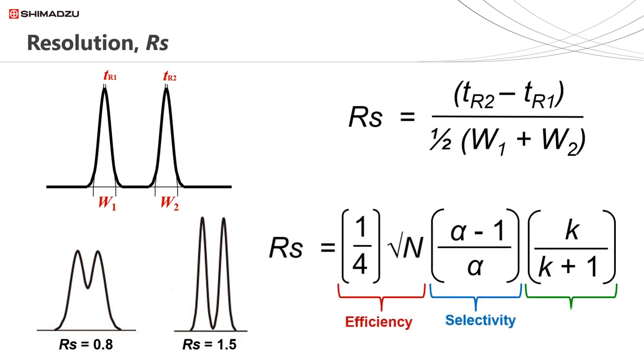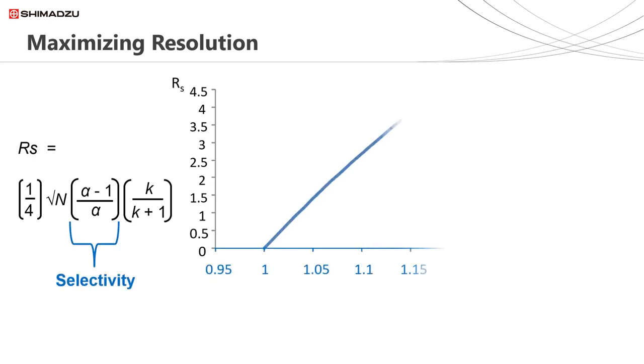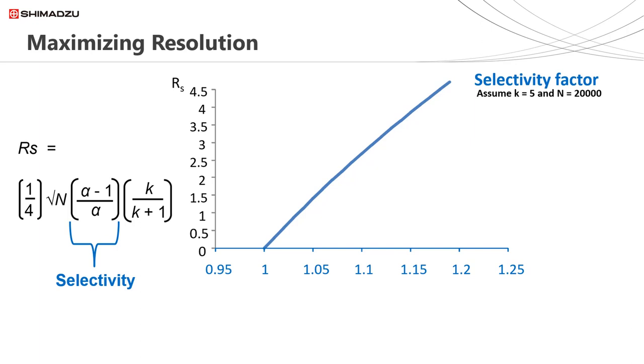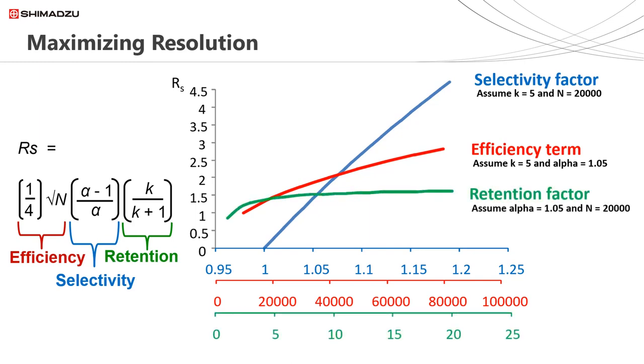The equation for resolution demonstrates how efficiency, selectivity and retention all contribute. Selectivity has the largest influence on resolution at higher values. As we looked at in session two, separation or selectivity can be changed by switching stationary phase, mobile phase, pH and temperature. Efficiency also has a large influence, but because of the square root term, doubling the efficiency only increases resolution by 1.4 times. Increasing efficiency involves minimising the effect of band broadening in our columns. Retention only has an influence on increasing resolution at lower values — ideally the retention factor should be greater than 2 and less than 10. Beyond 10, it has no further influence on increasing resolution.